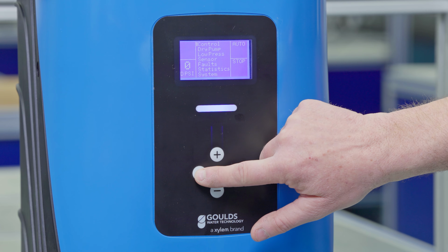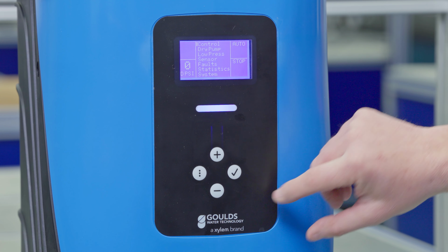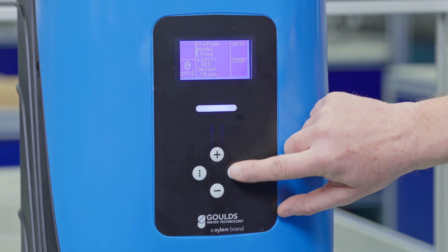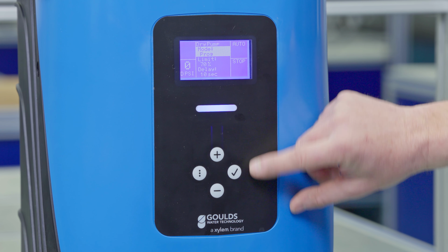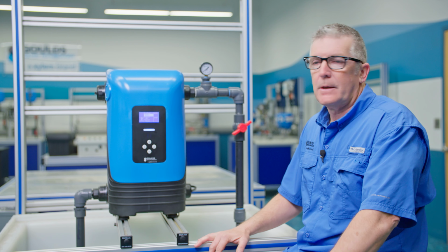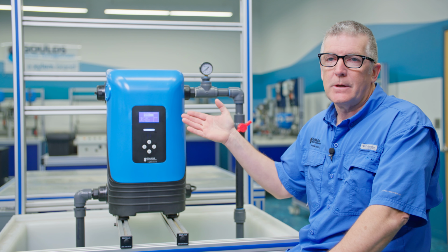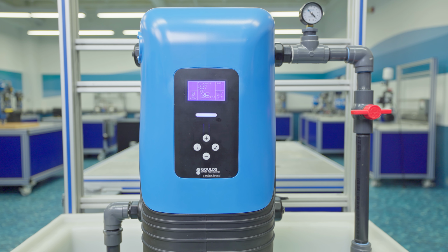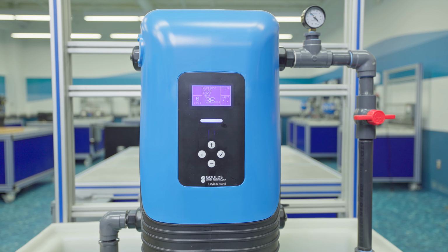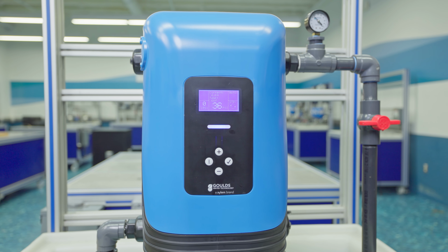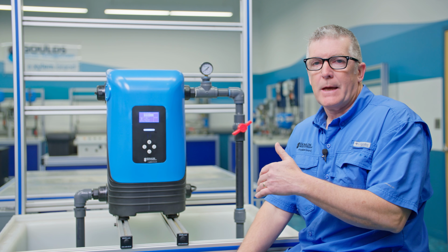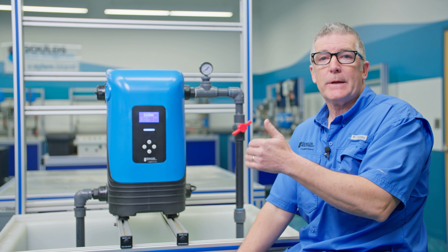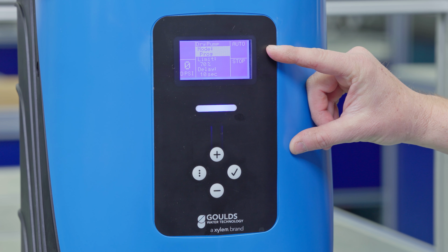So let's go back, and so that is it for control. The next one is dry pump. So let's get into that. Let's open that up, and the first option that you see here is what mode do you want? Now again, the default right out of the box is progressive. And progressive just basically means that if the unit faults on dry well, right, low water, dry pump it's called here, then progressive means that the time to restart progressively gets longer after each fault. So again, the default mode is progressive.